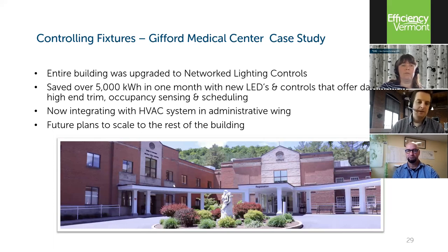There was one question about the difference between standard occupancy sensors and dual sensors, and when it's appropriate to use one versus the other. For folks who weren't following the Q&A, dual sensors can perform daylight sensing as well as occupancy sensing. So an appropriate use of a dual sensor is what was just mentioned a moment ago: if your light fixtures are in an area with access to a lot of daylight, consider sensors with both occupancy and daylight sensing functionality. If they're not in such an area, then an occupancy sensor would likely be more appropriate.